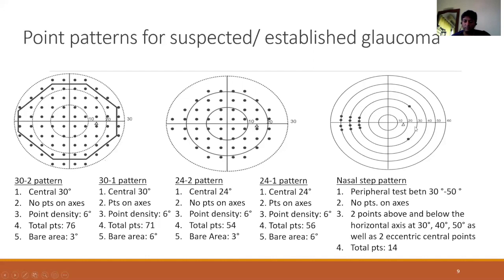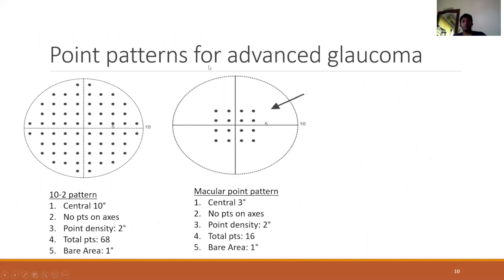The nasal step pattern covers a total of 14 points. Point patterns used in advanced glaucoma are mainly the 10-2 and the macular profile. The 10-2 covers the central 10 degrees, has no points on the central axis, point density of 2 degrees, 68 total points, and a central bare area of only 1 degree. The macular program is used for very advanced glaucoma to detect macular split; it is distributed only in the central 3 degrees, with no points along the central axis, 2-degree point density, 16 total points, and a 1-degree bare area.